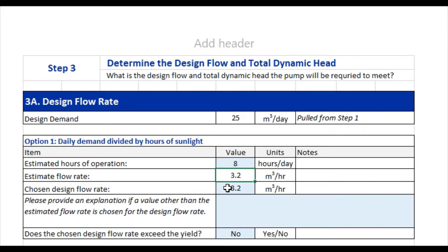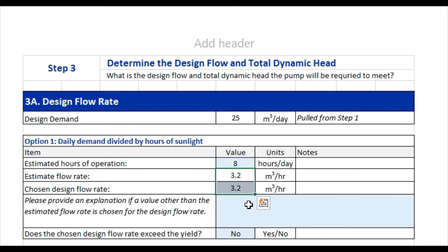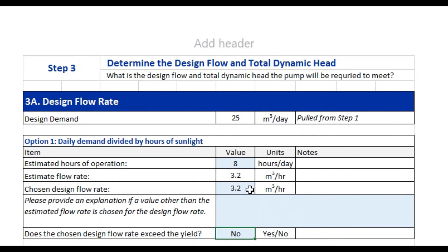Then you would enter your chosen design flow rate — either the 3.2 calculated above or option two, the safe borehole yield from step two. In this case we're going with 3.2, and if necessary you can provide an explanation if these two numbers differ. It's very important to ask whether the design flow rate exceeds the yield, because we can't go above the safe borehole yield. In this case, 3.2 is less than the safe borehole yield, so the answer is no. Our design flow rate is 3.2 cubic meters per hour.